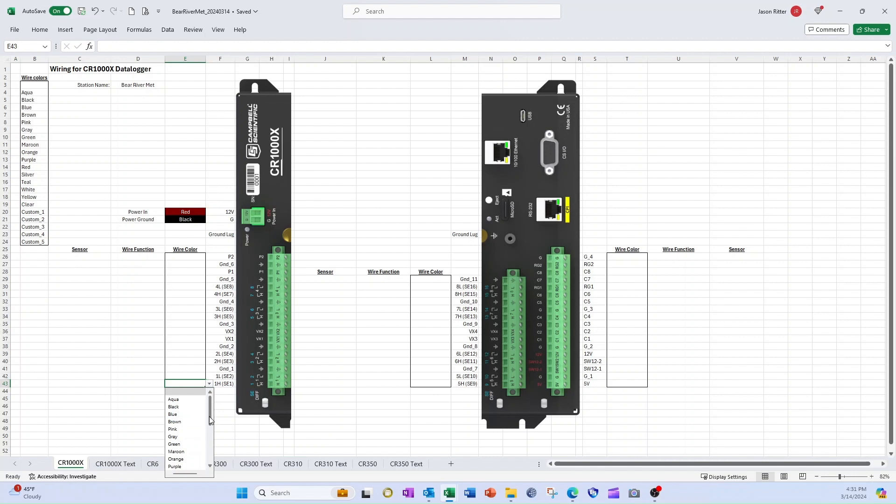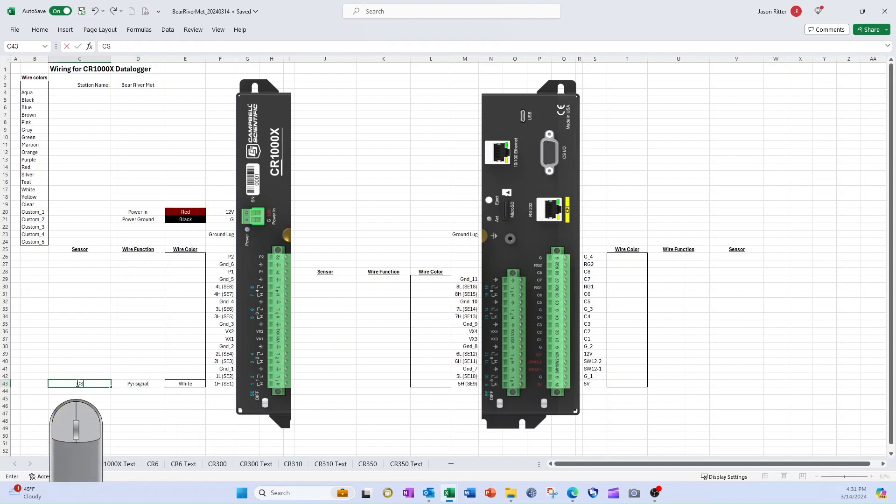My photo of the wiring panel shows that the CS301 pyranometer has a white wire connected to channel 1H and black and clear wires connected to the same analog ground channel next to channel 1L. I select the cell next to 1H and a drop-down arrow appears. When I select the drop-down arrow, the colors are listed in the same order they are found in the section called wire colors. I scroll to the color white and select it. The white wire is the signal wire for the pyranometer, so I enter that information in the cell to the left of the color. I enter CS301 in the sensor column.